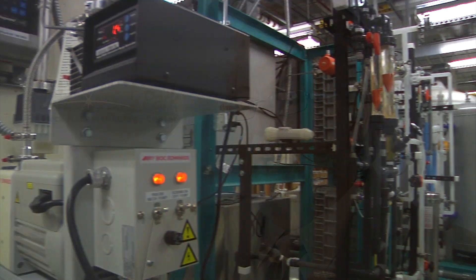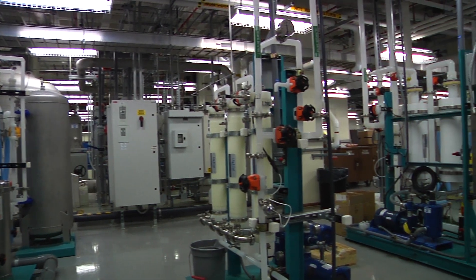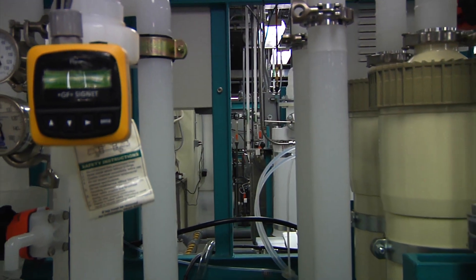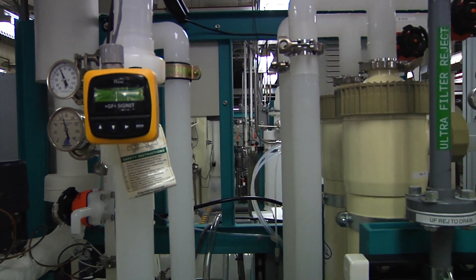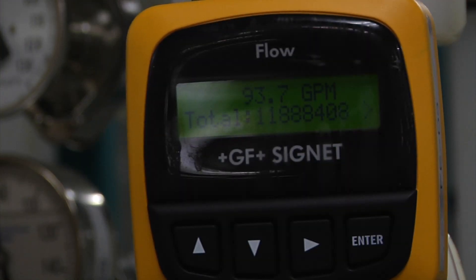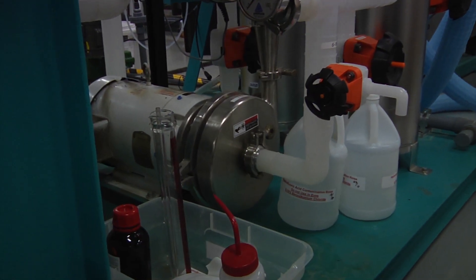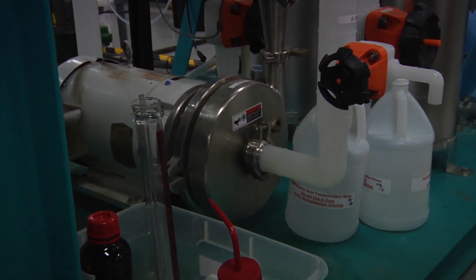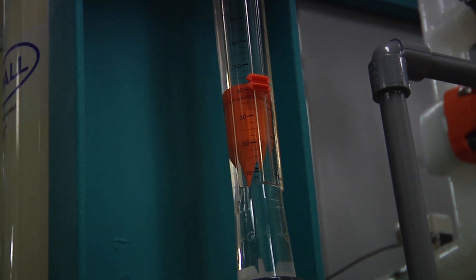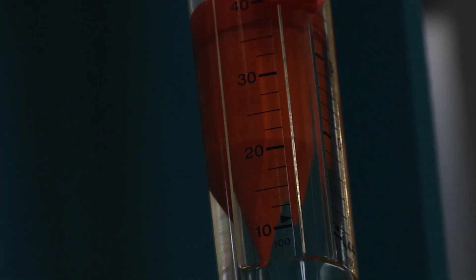Another unique feature of the BNC is the quality of the process water. The BNC ultra-pure water, termed nano-grade water, pushes the state of the art in water purification. Most deionized water operates at 18.2 megohm, which is the theoretical resistivity of water. You can measure impurities in water by the amount of electrical current that it will carry, because it's only impurities that carry the current. Pure water won't conduct electricity. This theoretical resistivity of 18.2 megohm means that you've got very pure water.